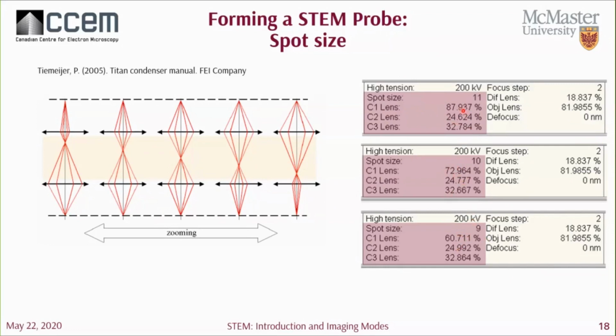They use a system which they refer to as a condenser zoom system, in which the image between the two lenses can be varied, but the position of the image in front of the first lens and the image after the second lens remains the same. So in choosing the spot size, the first step, we actually change all 3 of these lenses, and they work in conjunction so that the image formed after the C3 lens remains fixed. Imagine you have a C3 lens down here. As we change C1, the position of the image here doesn't change.